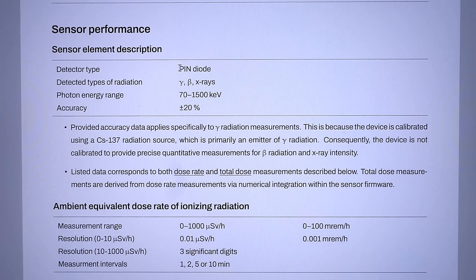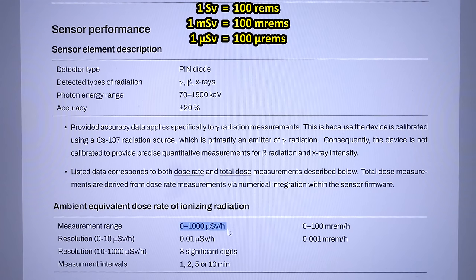It's using a pin diode as a detector, so it's a solid state detector instead of a Geiger counter tube. It's sensitive to gamma, beta and X-rays, calibrated using gamma radiation from cesium-137. It measures the dose rate from 0 to 1000 microsieverts per hour, or 100 millirems per hour.